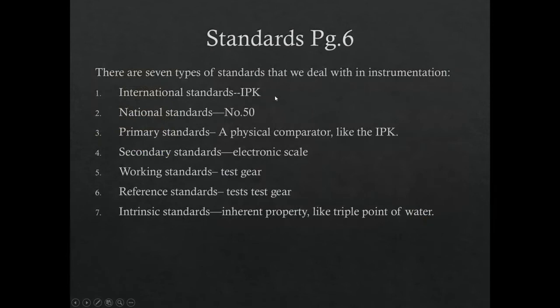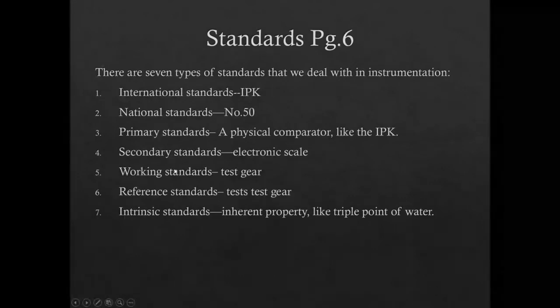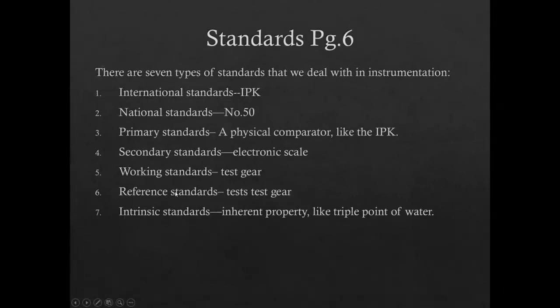Different standards we deal with in instrumentation: international standards cover things like the International Prototype Kilogram; national standards and primary standards are the bigger ones we probably never see. Then there are secondary standards, working standards — which cover our test gear — reference standards that test our test gear, and intrinsic standards, which have a physical property that doesn't change, such as the triple point of water or the temperature of ice water.